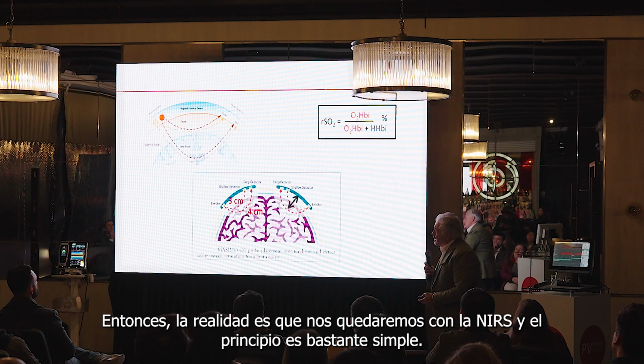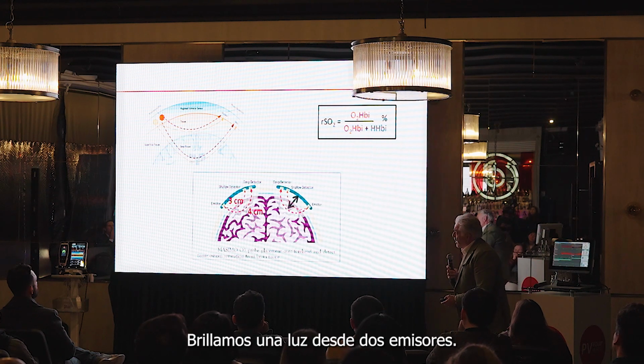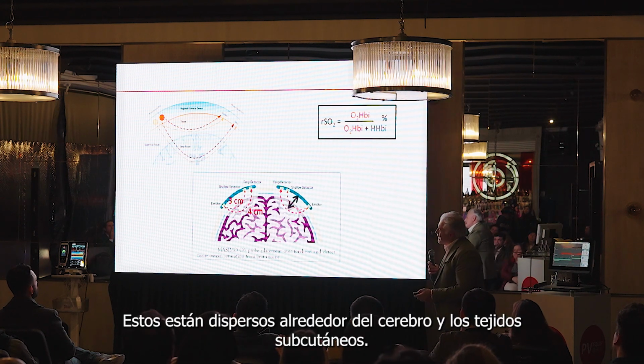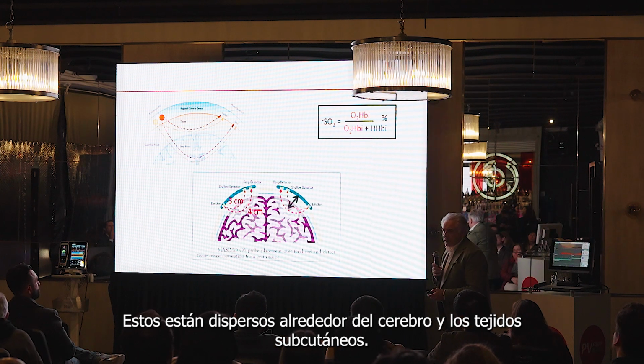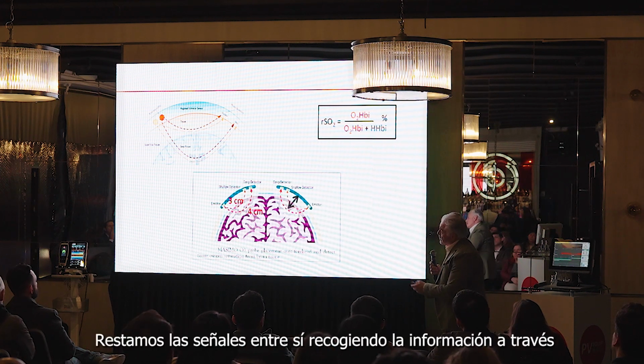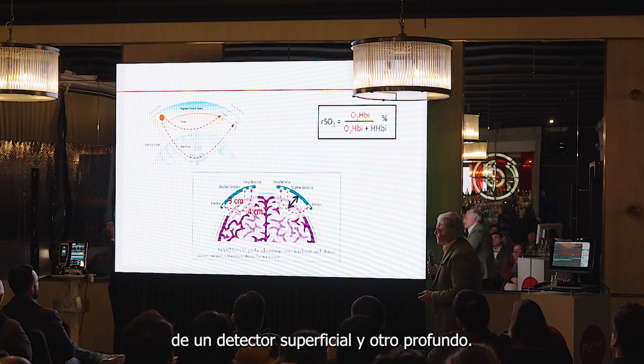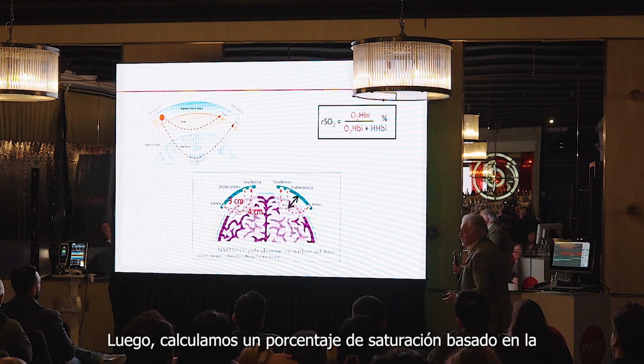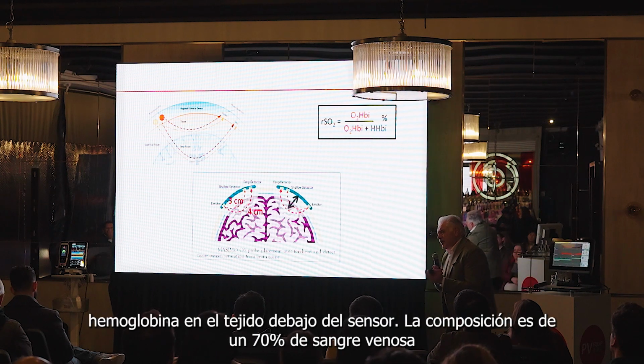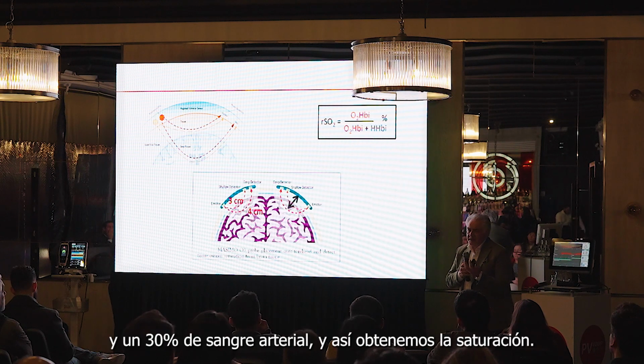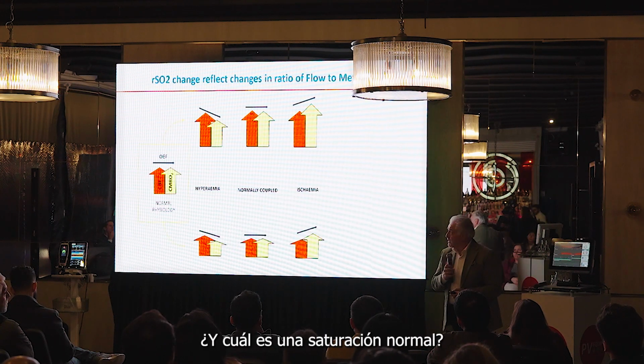And the principle is quite simple. We shine a light from two emitters. They scatter around the brain and the subcutaneous tissue. We subtract the signals from each other by picking up through a shallow and deep detector. And then we come up with a percentage saturation, based on the hemoglobin or tissue underneath that sensor being 70% venous and 30% arterial. And you come up with the saturation. And what's a normal saturation?